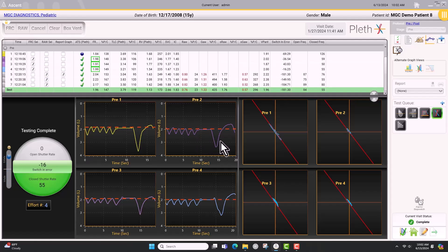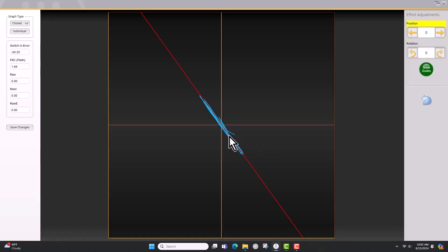If a tracing needs adjustment, double-click on the graph to bring you to the adjustment screen. Always check the line of best fit before selecting efforts to average. Selecting an effort that has an inappropriate line of best fit will cause your lung volumes to be inaccurate.